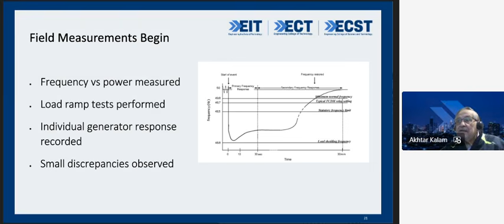Now, my friend, you can see some discovery you have made. One of the two generators, say A and B, one of them drooped by 4% and the other one had 1% droop. If it's less than 4%, they're all within acceptable limit, so there's no problem. But the problem is that as one drooped 4% and the other drooped 1%, compatibility was not there. Can you understand that? Compatibility was not there, my friends.